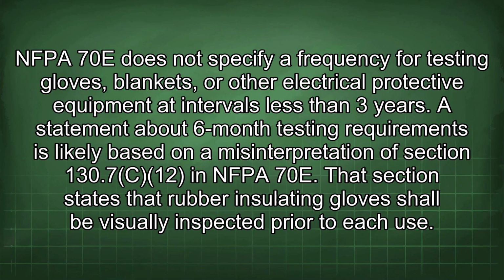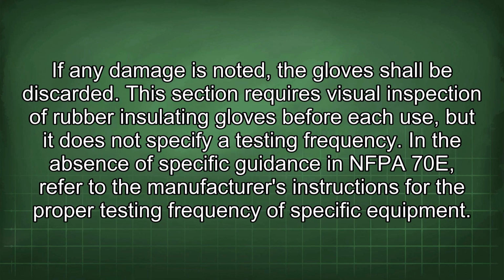NFPA 70E does not specify a frequency for testing gloves, blankets, or other electrical protective equipment at intervals less than 3 years. A statement about 6-month testing requirements is likely based on a misinterpretation of Section 130.7(C)(12) in NFPA 70E. That section states that rubber insulating gloves shall be visually inspected prior to each use. If any damage is noted, the gloves shall be discarded.